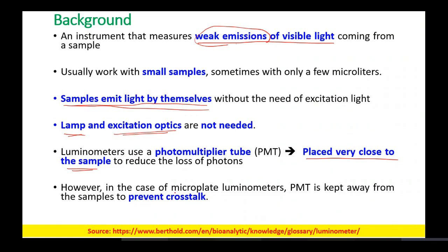However, in the case of microplate luminometers, the PMT has to be kept at a distance to prevent crosstalk, and we have also talked about this, because if you see the previous point, this point number 5 and point number 6, they are in contradiction.